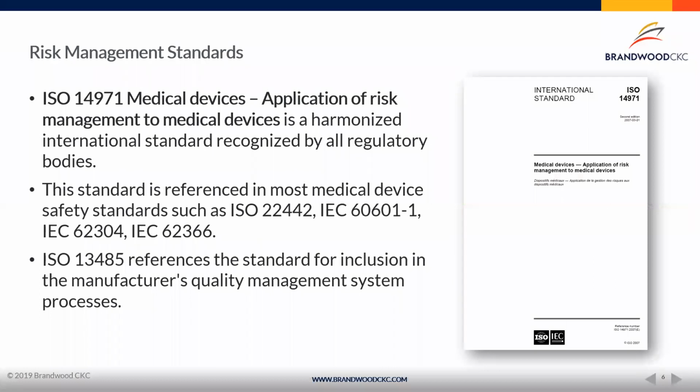Risk management standards, as we started off, ISO 14971 is the big boy here. This is the application of risk management to medical devices. The unique thing about 14971 is that it's truly a harmonized international standard, and it's recognized by all regulatory bodies. So in that respect, it's kind of a unicorn. There aren't a lot of ISO standards or standards in general that are going to be consensus standards.